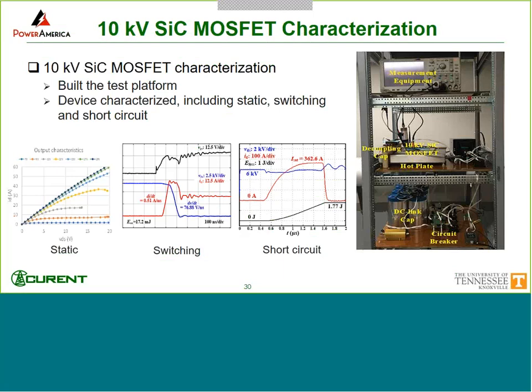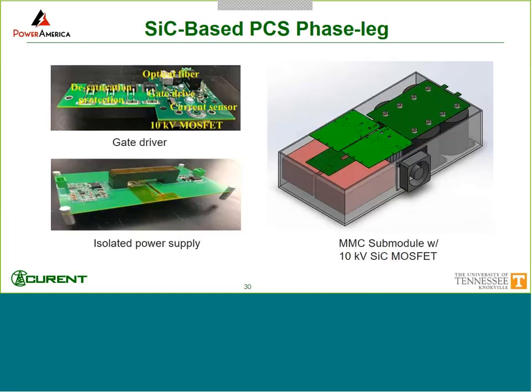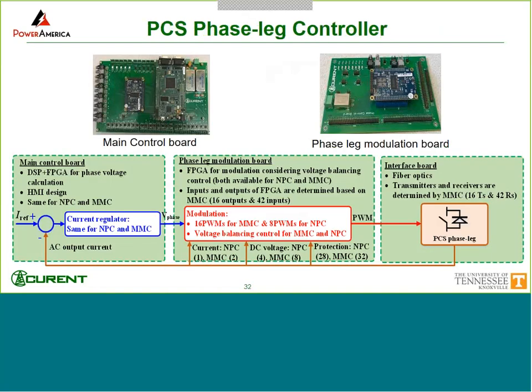At this point, we have finished the device characterization. We have got all the device modules needed for the converter for the first year, and developed the gate drive, the protection, and also the isolated power supply for it. This is just an example of some of the testing we have done, the double pulse test. And this shows the gate drive, the power supply we have developed, and also a mechanical drawing of how one of the sub-modules would look. The controller has already been developed for the phase leg module, and because we already have an MMC and other converters at UTK, we could leverage many of those.